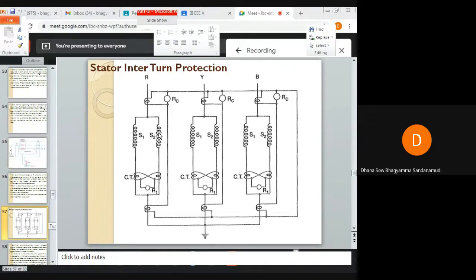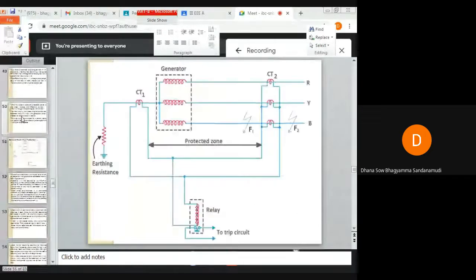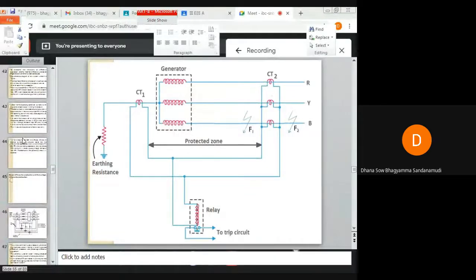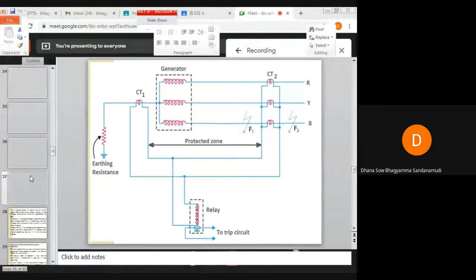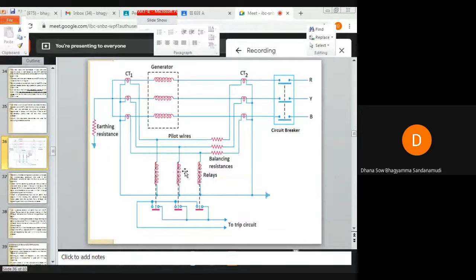So merz-price protection is able to protect against phase-to-earth and phase-to-phase faults, but not against interturn faults. Why? Because the current through this type of fault produces flow in the local circuit between the turns involved, and does not create any difference between the currents entering and leaving the winding at its two ends where current transformers are applied. Okay, this is our merz-price protection.